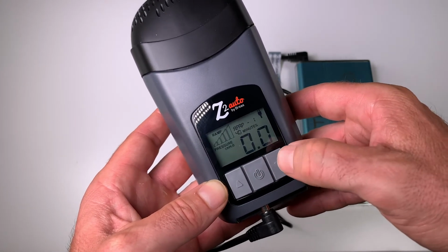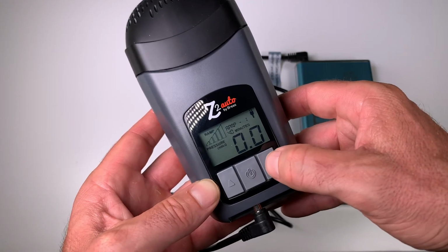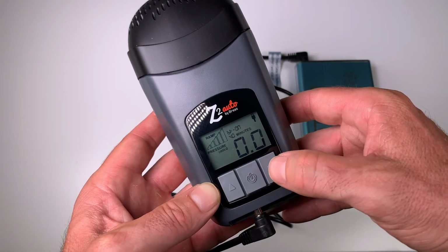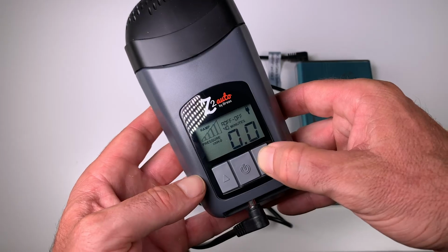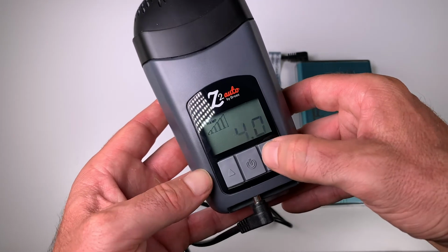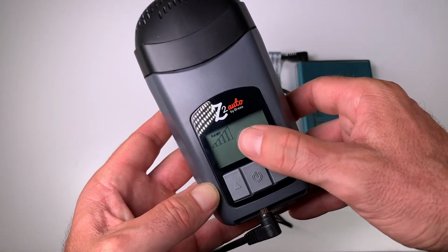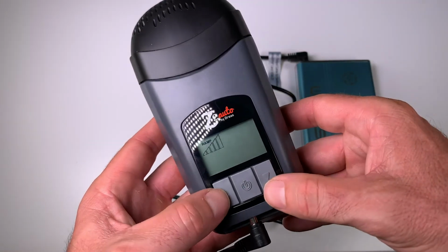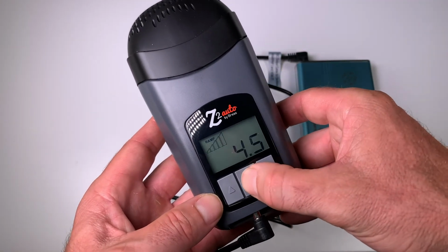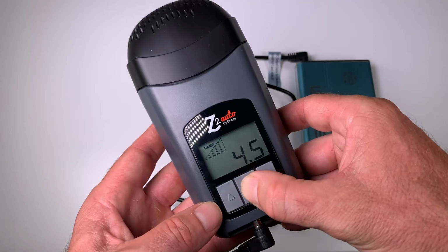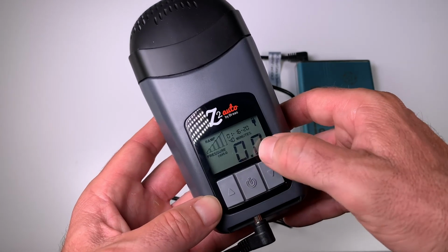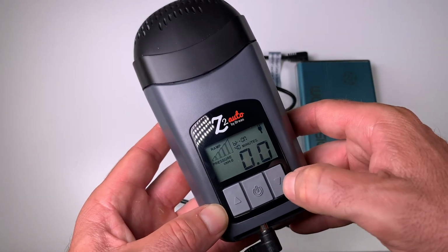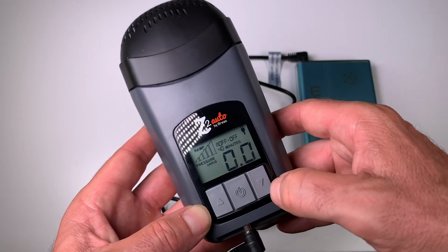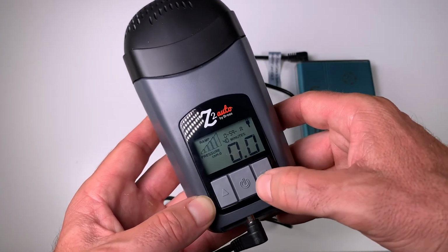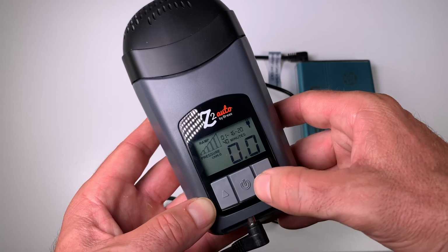Now the other part we can change here is the ramp start pressure. So press and hold down the down arrow, press and hold it down. And you can see here, this is where the ramp's going to start from. Okay, so I might bring that up to 4.5. Now just be aware that the number that I just put in, 4.5, has to be lower than whatever the automatic min pressure is that you set. So we set our auto min before to 5.